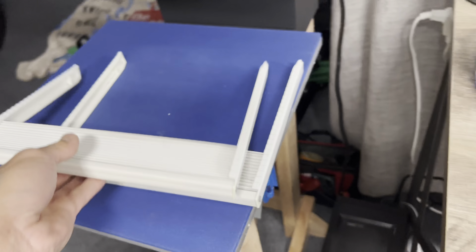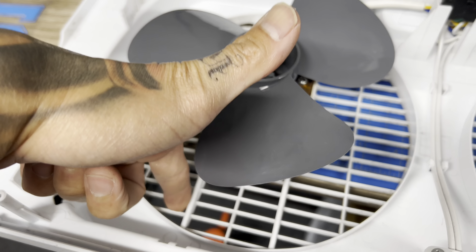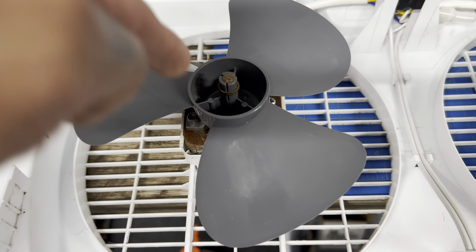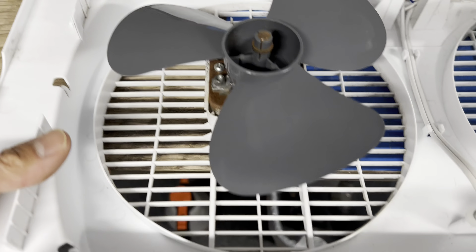It's all cleaned up — even cleaned these fins. One thing I noticed is there's an airflow problem. When it pushes air through, it's sucking air from everywhere including the sides. When it's pushing air out, the air hits the wall and creates turbulence — it cycles back and some of the hot air coming in through the back hits the guard and recirculates. So there's a lot of turbulence in there. We need to create some type of funnel so when it's sucking air in, it pushes all the air straight down.